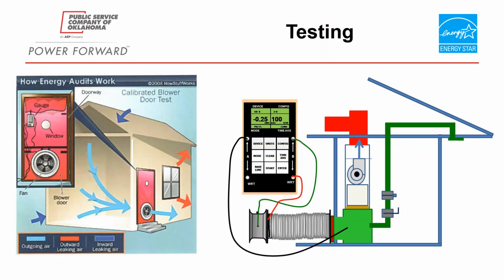The one on the right here is a duct blaster. Basically it's exactly the same thing as the blower door, only we connect this equipment to the ductwork and HVAC system. When we fire this up, we pull that down to a 25 Pascal pressure, and we can figure out not only how big the holes are and where they are, but we can help direct contractors to the biggest holes and figure out how to fix those. There are various different ways we'll get into in a minute.